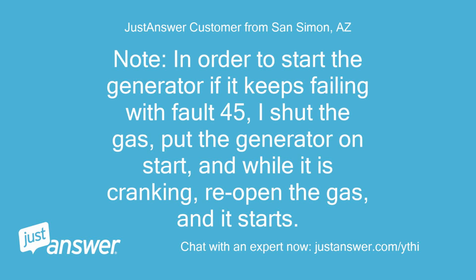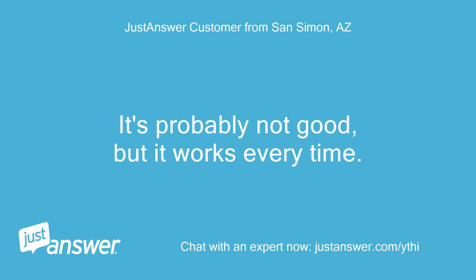Note: in order to start the generator if it keeps failing with fault 45, I shut the gas, put the generator on start, and while it is cranking, reopen the gas and it starts. It's probably not good, but it works every time.